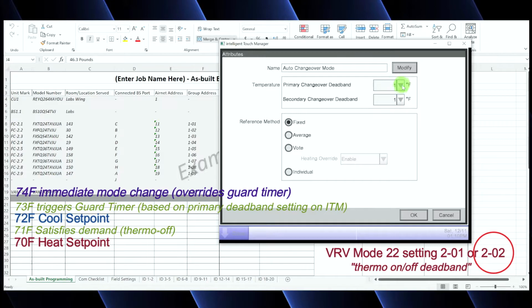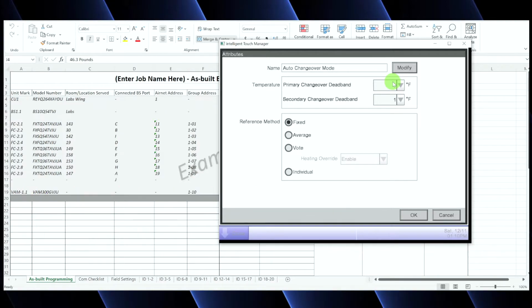So you want to try to set up the primary changeover deadband based on how you want that system to operate normally. If you're going to have a 70 degree heat set point and you're going to have a 73 degree cool set point, that means at 74 degrees, it's going to start the guard timer. And then once the guard timer has expired, it will then change modes. So you might have to play around with this a little bit. Just be careful not to set this at 1 degree when you have a single set point. Otherwise, you're going to have problems.